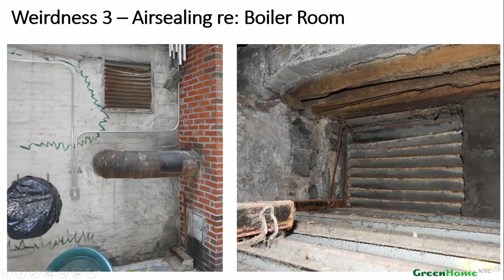Okay, so this is the air louver for the boiler room, the existing boiler, and it's actually probably oversized. But what we found out when we stuck our head above the ceiling in the boiler room was that a good two-thirds of the louver was dumping cold air into the area above the boiler room ceiling. It was making the floor of the first floor apartment really cold. So we ended up recommending that they install a new ceiling above the top of the louver, so that we could control that air intake a little better, because as it was set up, it was a giant stack effect problem that was going to make people uncomfortable.